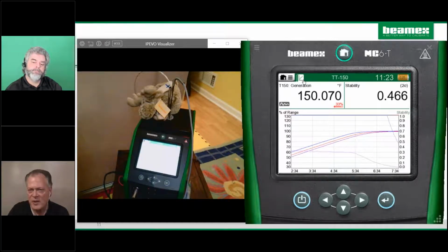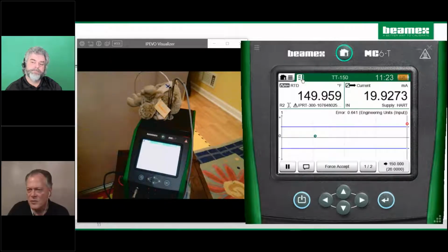So we'll come back to this screen, but let's look over here. Because of this lag, we're still showing error of over ½ degree. And by the way, this is a pretty tight tolerance here, ½ degree. So it's kind of pushing the limits of the equipment we have today. But look, it's getting closer. It's catching up to the milliamps, and now we're less than ½ degree error, and it went green. The fact that this is still moving, we want to wait for things to get a little more stable.